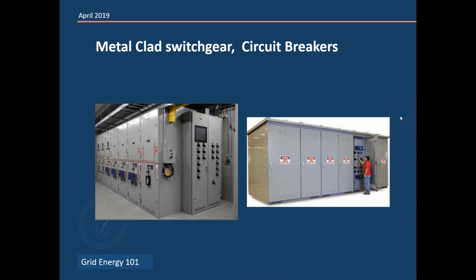Can a separate entity own a substation? So I think it's kind of like saying, rather than a utility owning the substation, could an end user own the substation, or a third party? Yes, absolutely. Someone other than the actual utility could own the substation. There are customer substations, and in a lot of cases in the Midwest specifically, there'll be substations where we own these three circuit breakers here, and the next three circuit breakers are owned and operated by a rural electric cooperative. So there are lines of jurisdiction where we know this is my equipment, this is that equipment, even though we may be in the same substation. So absolutely, that's definitely a possibility.